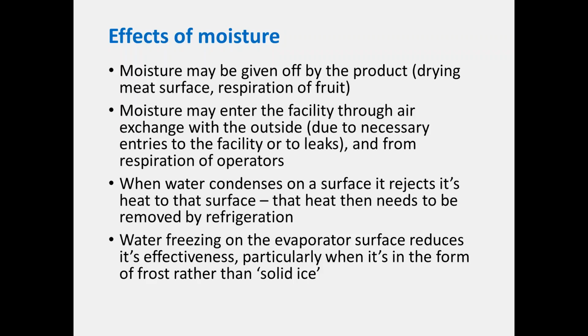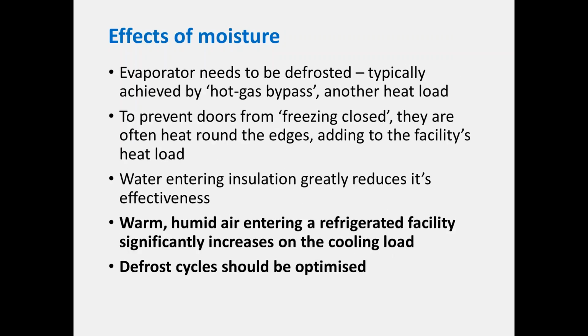If when it freezes on the evaporator, it's a solid ice shell, that may not be so bad, but often it's just going to be like frost, like snow, which will trap air and again greatly reduce the performance. So that's why you need to defrost periodically. Simplest way to do that is with hot gas bypass, but that's yet another heat load. And there are guidelines for optimizing your defrost cycle.